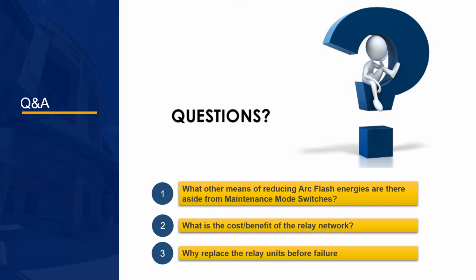Question 3. Why replace the relay units before failure? Assuming that spare relays are readily available in the event one fails, you still have to deal with the repercussions of a relay failure. If the relay that fails was non-critical to plant operations, any repair activities would have to be done on a live gear. If the relay that fails is critical to plant operations, then you have to handle an unscheduled outage to repair, losing generation time and potentially costing you far more than the relay is worth. If you replace the relays during a planned outage, then the relays are likely to pay for themselves by improving reliability and reducing the chances of an unscheduled outage.